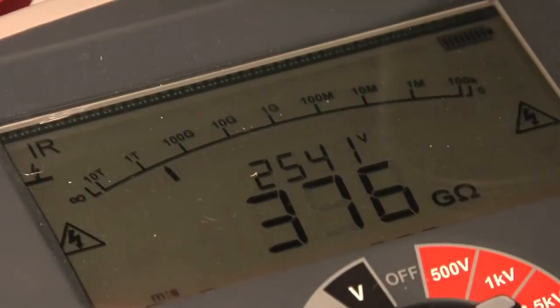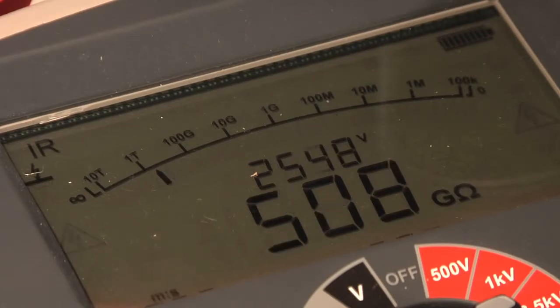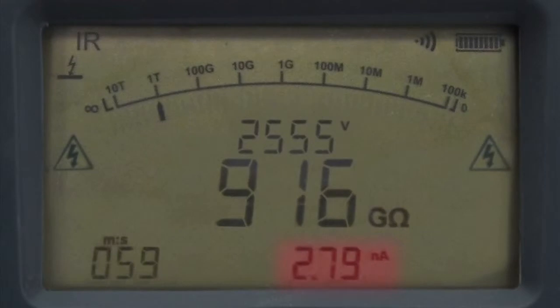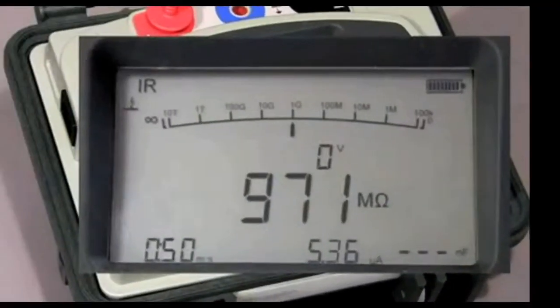It gives you additional information. The actual applied test voltage is displayed. The test item will always load up in voltage a little bit, so you'll get an actual test voltage slightly higher than your selected voltage, and you can see that. It also shows you the reciprocal of resistance, which is the leakage current. So you can look at the leakage current directly, and it gives you the added capability of seeing some simultaneous information for your interpretation. And finally, there's a timer.